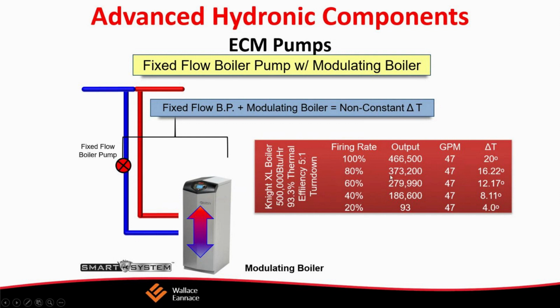You can interface with these pumps either using an RS-485 cable, and it connects with an application that's available free of charge from Xylem. Or you can also use a wireless module. It doesn't require any software. You just need a web browser. You put the wireless module in there, link up to it with your phone, and then use a browser for controlling all the parameters on the pumps. It's pretty simple. There's a code on the side of the pump. Plug it in. You're ready to go.